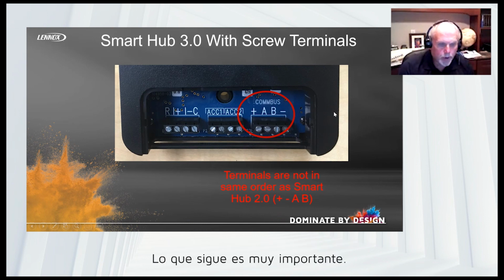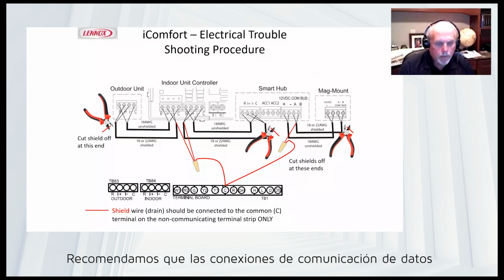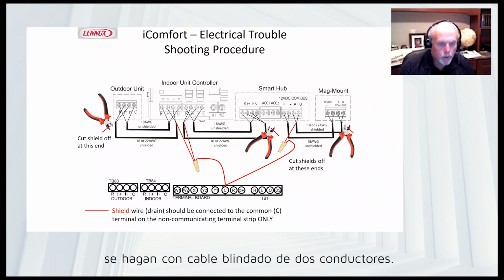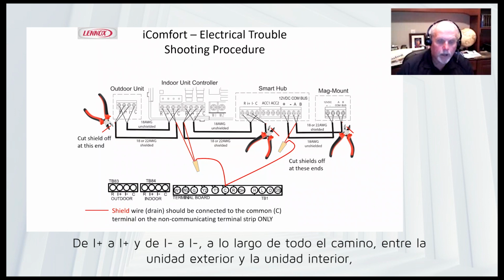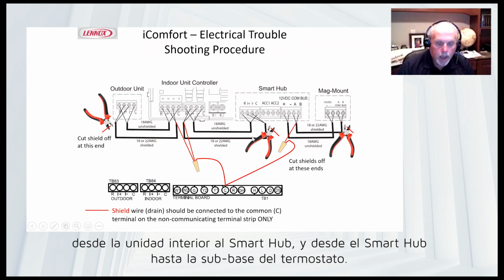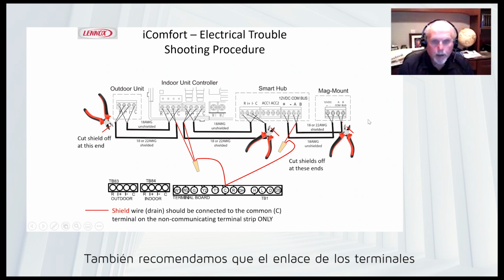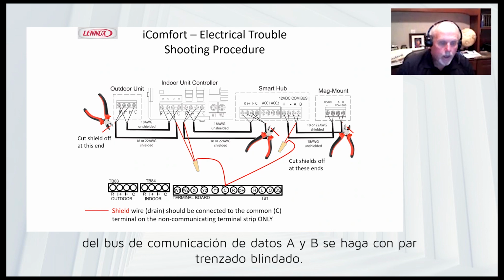So this is very important here. We are recommending that we run our communication wiring in two conductor shielded wire. The I plus, I minus, all the way through outdoor unit to the indoor unit, from the indoor unit to the Smart Hub, and from the Smart Hub up to the sub base on the wall. The communication bus would be highly recommended to run twisted pair shielded stranded wire.